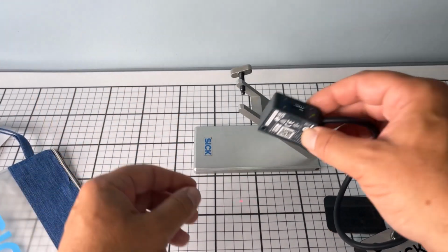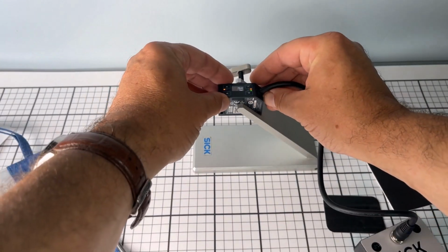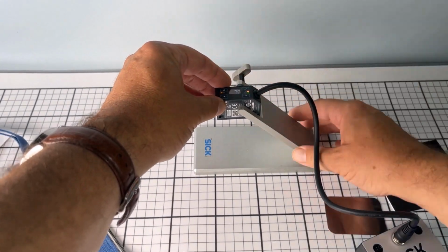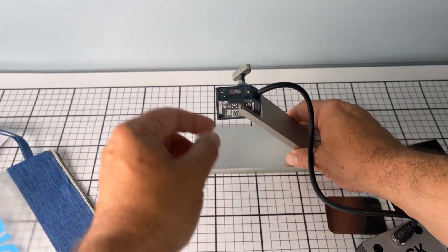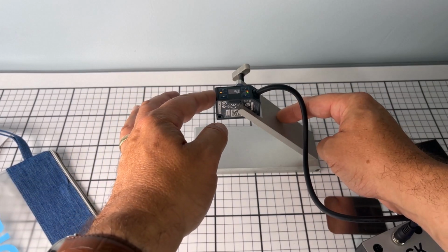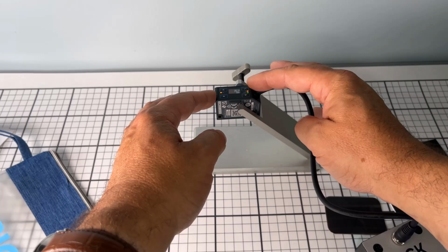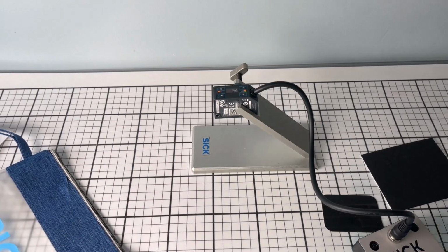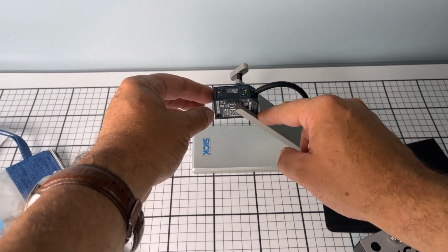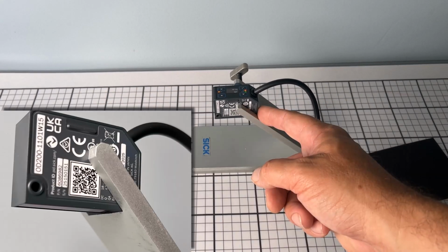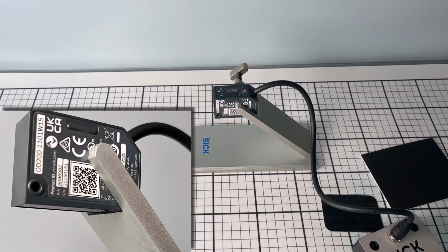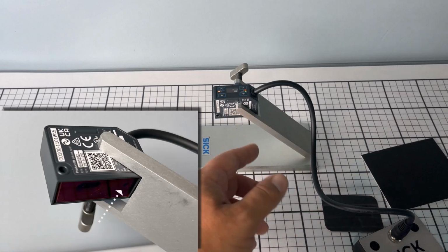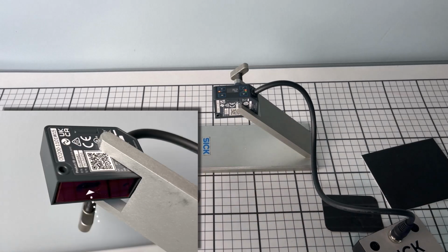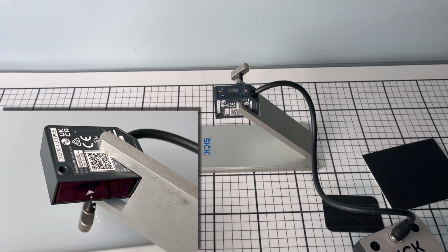Let's start by mounting the sensor. Secure it to a mount or stand that limits the amount of travel or movement or flex. We're measuring sub-millimeter changes, so setup is very important. I'm making sure there's an extra point of contact to keep it stable during operation. Just be sure the laser emitter and receiver stay clear. No part of the stand should be blocking the optical face of the sensor.